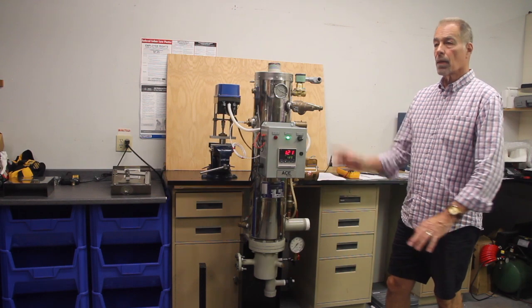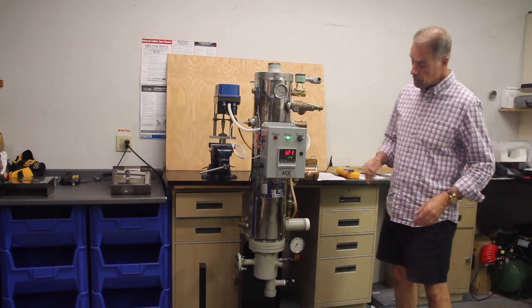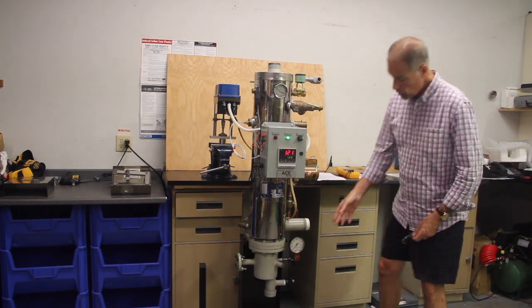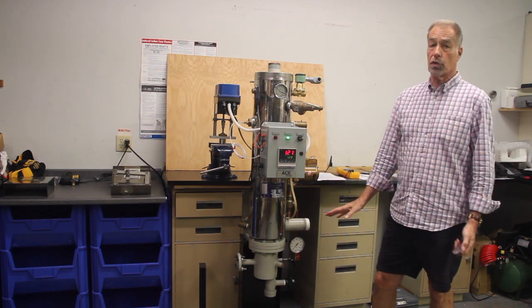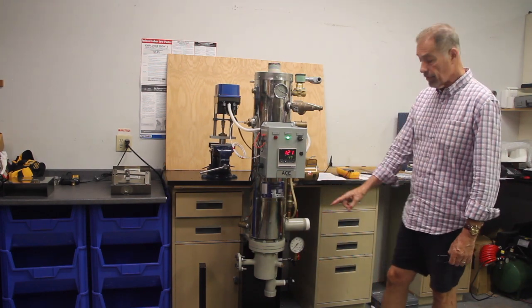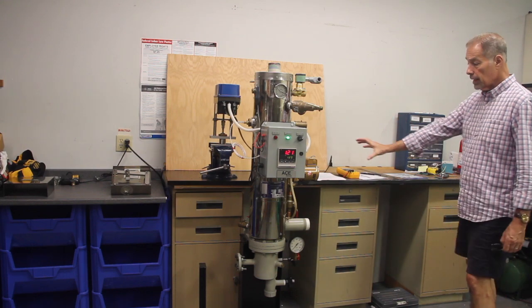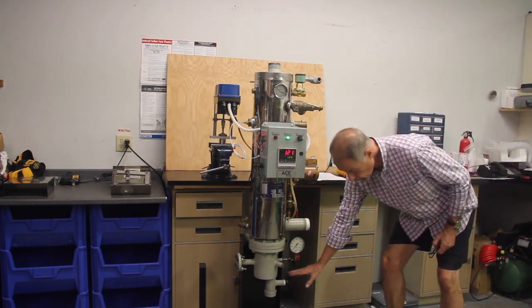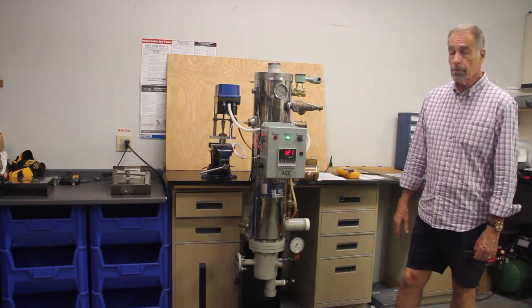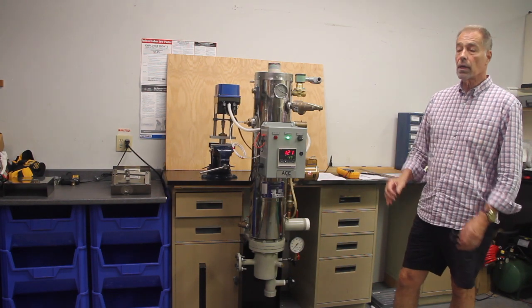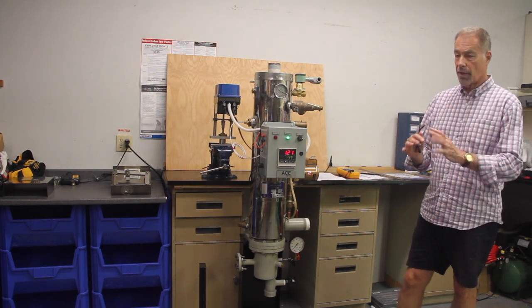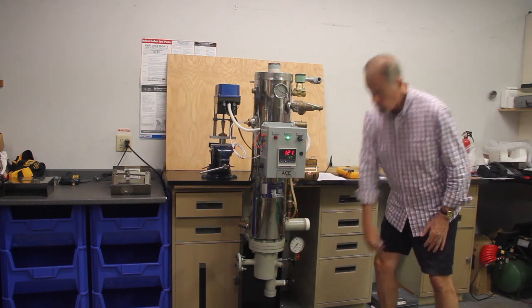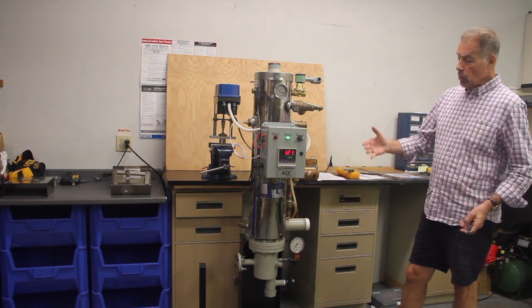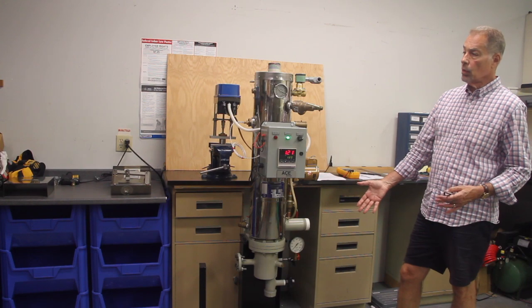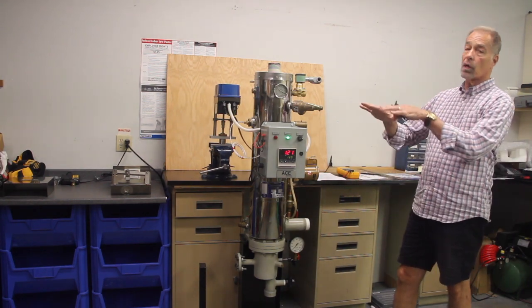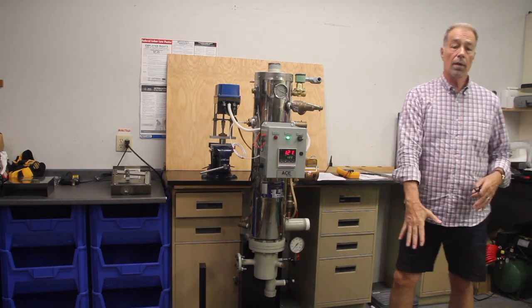Nothing will fail. I will tell you there's a downside to this feature, which is that when your condensate comes out of this heater, there's no pressure. So you cannot lift the condensate and get up into a condensate line that's above the invert of that outlet. We want to go by gravity to a vented receiver or to a gravity line that is below this elevation. So very often if we have a problem with elevation height, we can take this heater and lay it down and make a horizontal heater out of it so we have more drop.